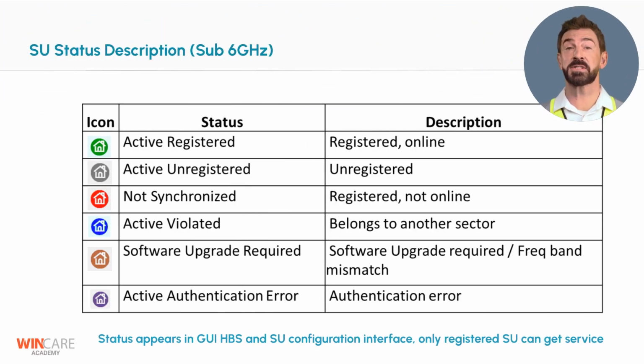These are the possible status icons displayed on the base station or subscriber unit management interface. Active registered: the subscriber unit is fully registered and service is available. Active unregistered: the unit is connected, but registration is not complete and service is not available. Not synchronized: the unit was registered previously, but it is currently offline. Active violated: the subscriber unit has a different SSID and therefore cannot receive service.